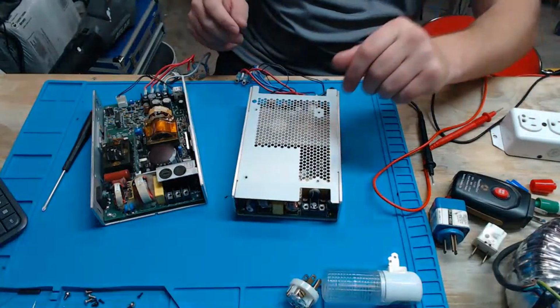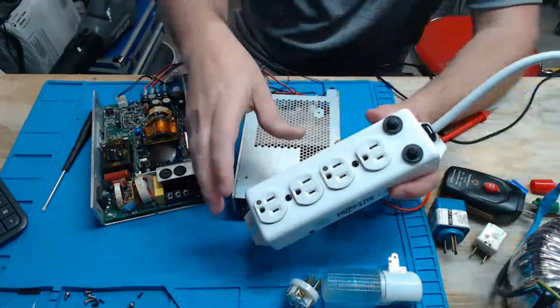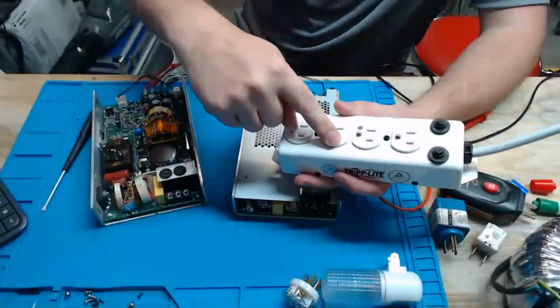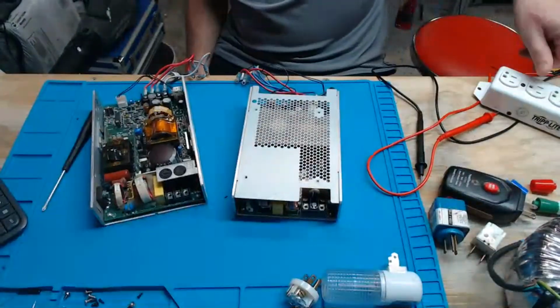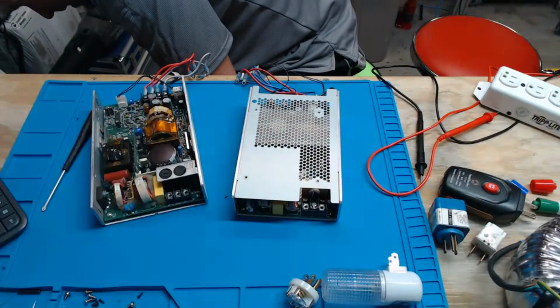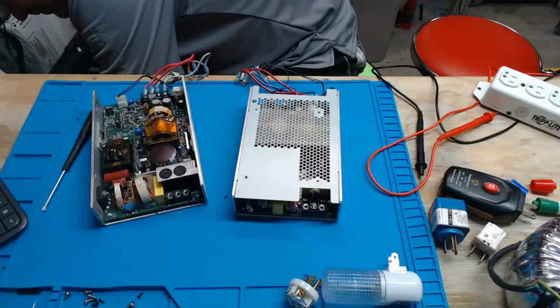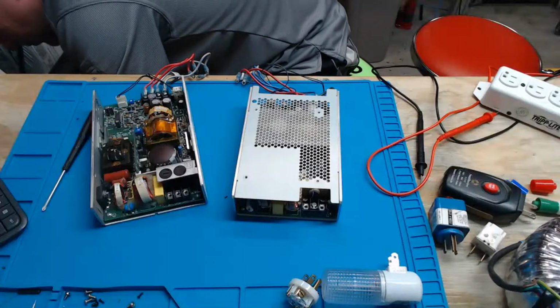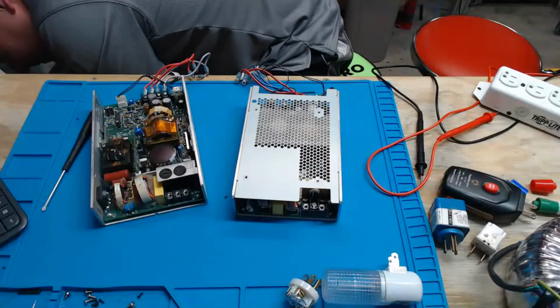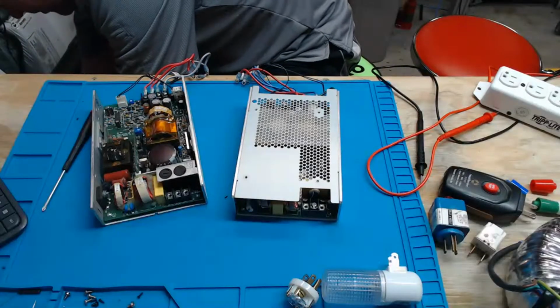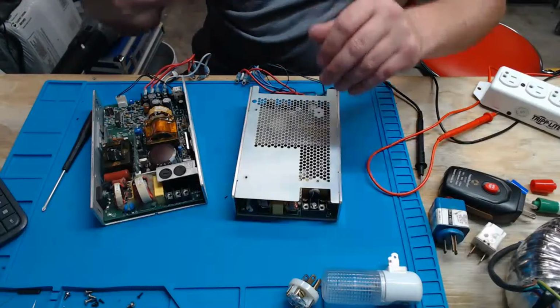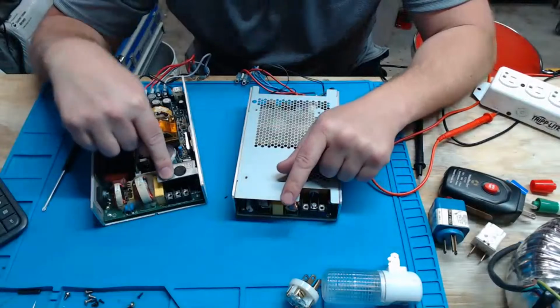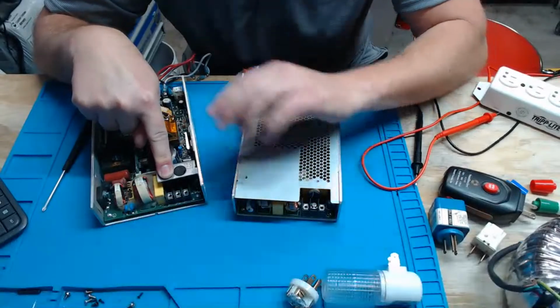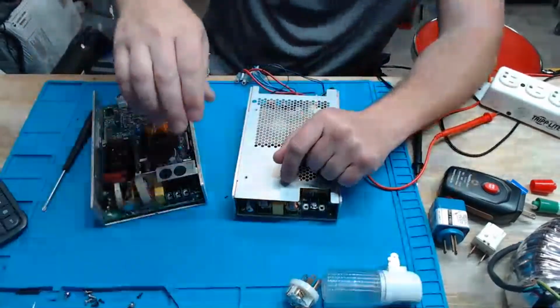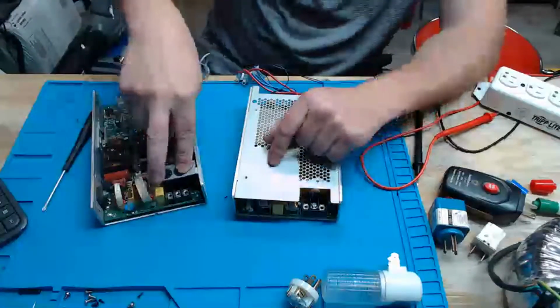And the reason that we do that is because of this guy right here that I showed you. We have voltage on both line and neutral, which is not normally the case. If you take a power supply that is non-medical grade, you will most likely only have one fuse, and it's only going to be on the line side, not on the neutral. I'm going to tear open a couple of those things very soon, guys. All right, so in a medical grade power supply, line and neutral are going to be fused.